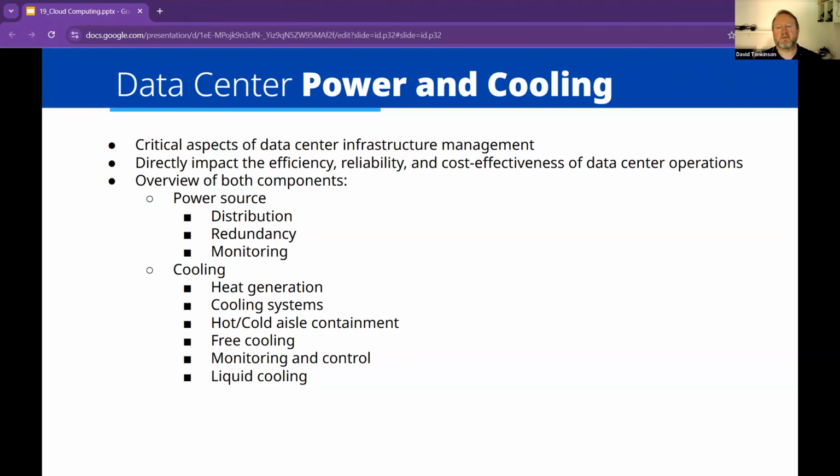To the extent where some data centers actually run what is called a 2N redundancy, meaning if they wanted 5 diesel generators to run their systems, they don't have 5, they have 10. Okay, so they double it up. They have twice as many generators, and they're probably on different sides of the building to make sure that they can run the system despite any issues, fires, or other damage that happens to the other locations. So that tends to be the power redundancy.